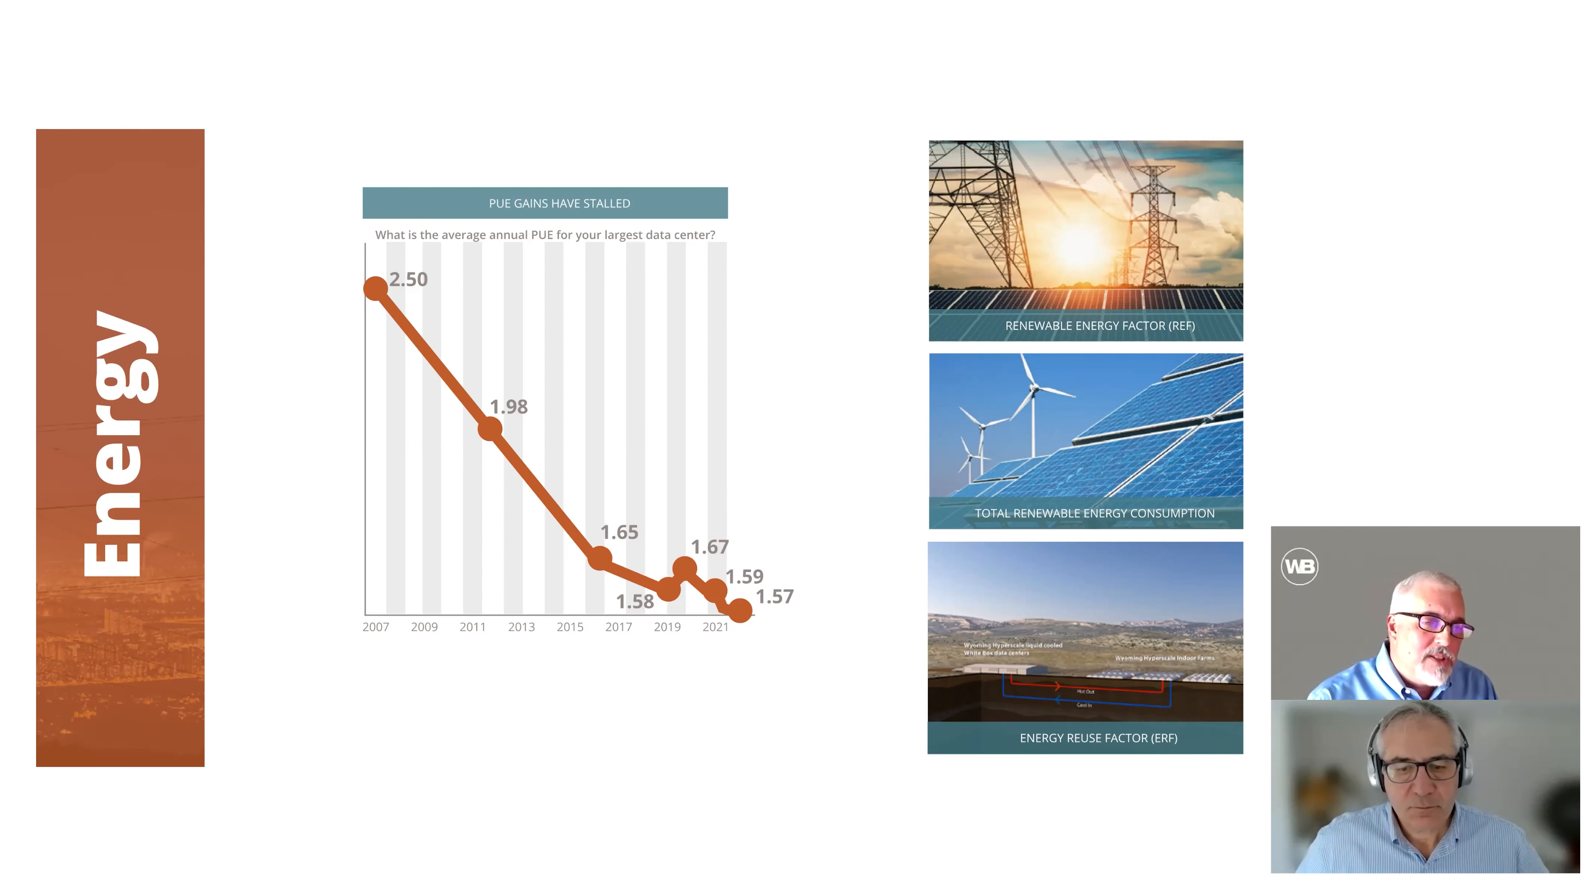And this was from Uptime Institute. They surveyed the largest data centers in the country. We don't design things to 1.57. I think most of the clients we're seeing now is in the 1.3 to 1.4 range. But these were the larger hyperscale guys. So you can see it's leveled off. So now we've got to figure out what's the next way to start reducing energy.